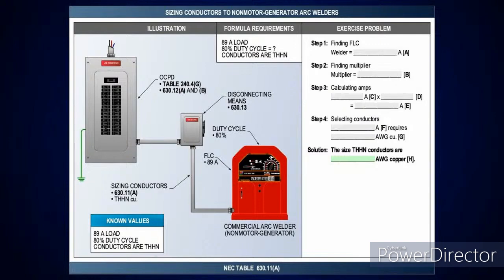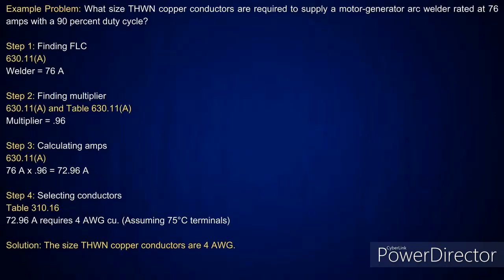Okay. And then when I get over here, this is a motor generator arc welder. Well, looky there, I'm doing the exact same type calculation. I've got 76 amps for the welder, and I've got a 90% duty cycle. I go look at table 630.11(A), and it's going to tell me. Now, I want to point this out. When I'm doing this for non-motor and motor generator arc welders, you're going to use table 630.11(A). But when I get over and I start looking for the resistance type welders, you're going to look at 630.31(A). We'll look at that in just a minute.